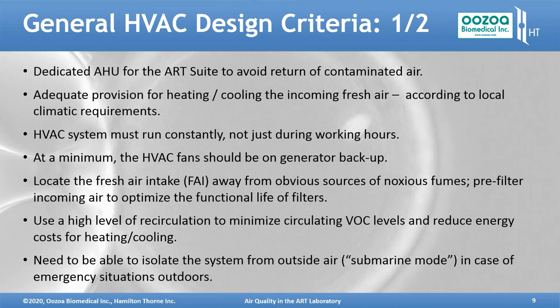You need to locate the fresh air intake away from obvious sources of noxious fumes, so not in loading docks, not near the helipad. And you need to pre-filter the incoming air to optimize the functional life of your high-grade filters in the clean room. Use a high-level recirculation to minimize the circulating VOC levels and to reduce the energy costs of heating and cooling. And you need also to be able to isolate the system from the outside world.